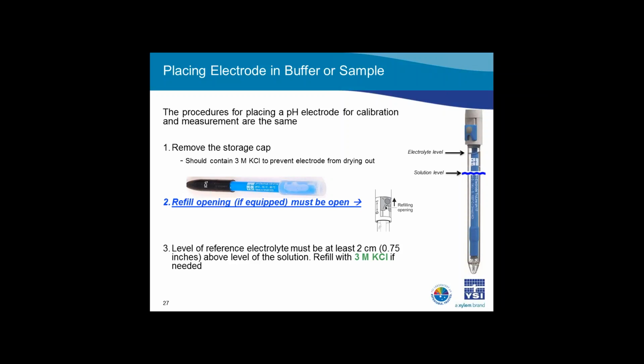Next, if using a refillable electrode, make sure the level of the reference electrolyte is higher than the level of the buffer or sample. The reference electrolyte should be at least 2 centimeters above the level of the solution that you're measuring or calibrating in. If it isn't, refill the electrode with 3 molar KCl or the electrolyte used by your sensor.